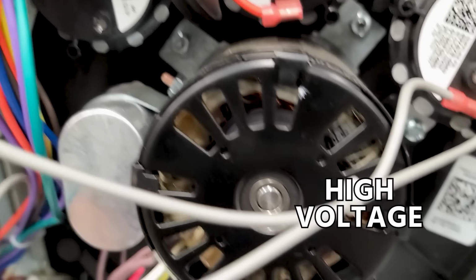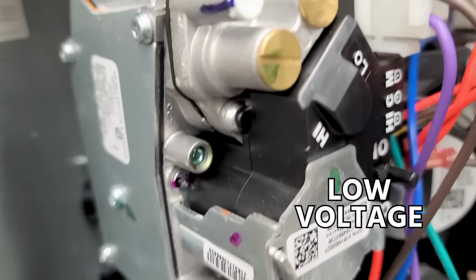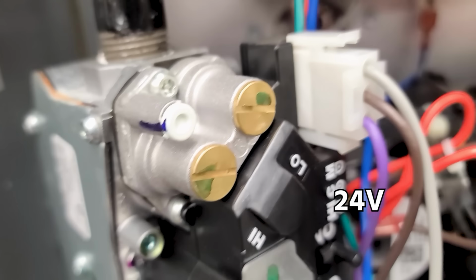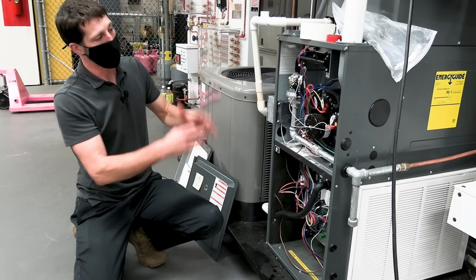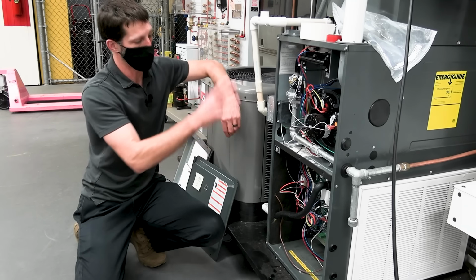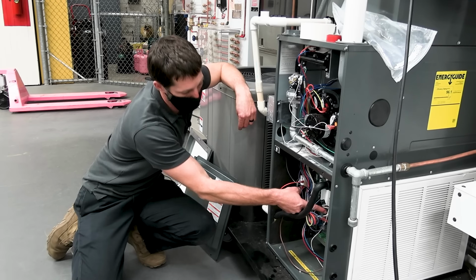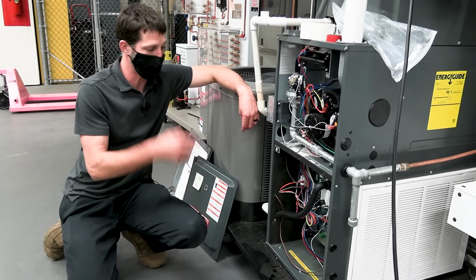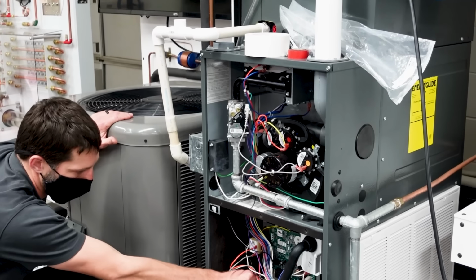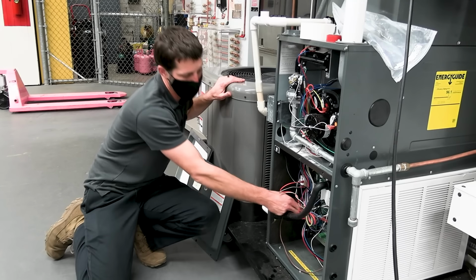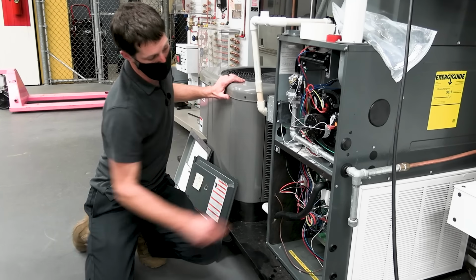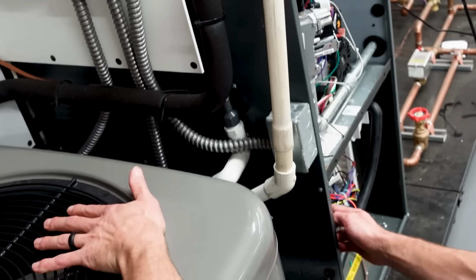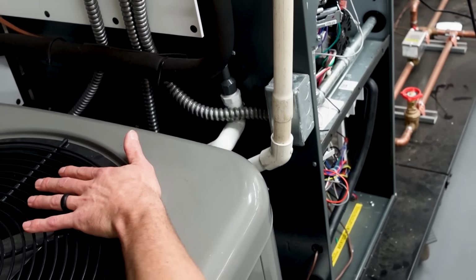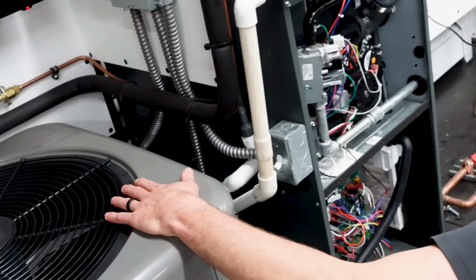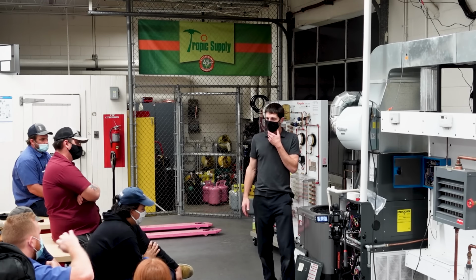This is high voltage, and this is low voltage, 24 volts. 24 volts is your control voltage, and it also powers devices, you know, on your gas furnace. Anytime you see a black box on the control board, that's usually a relay. Those are typically a DC relay instead of AC, when they're mounted, soldered on the control board. Transformers are always alternating current in, alternating current out. They do not rectify. That's why the doors usually have louvers on them.